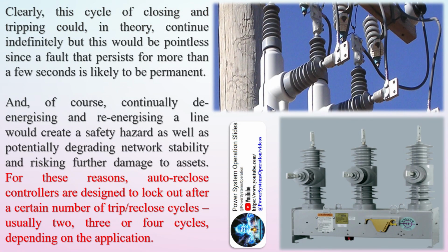The operating principle of an auto-recloser is equally simple. When a fault is detected, the breaker trips. The controller then waits for a predetermined time before reclosing the breaker.